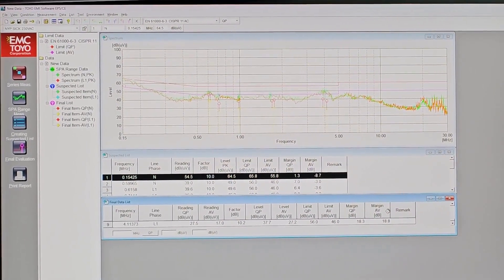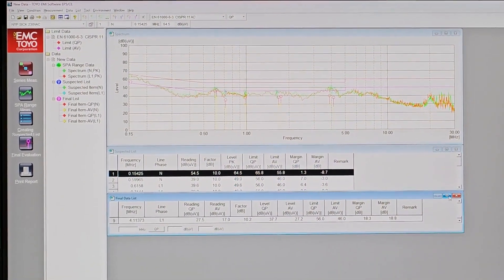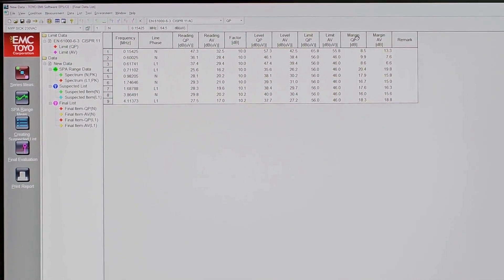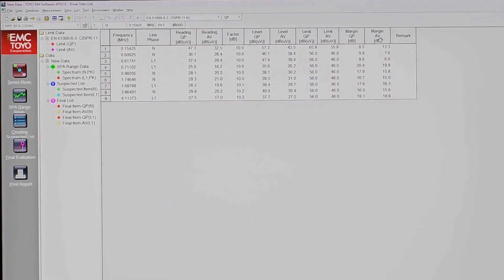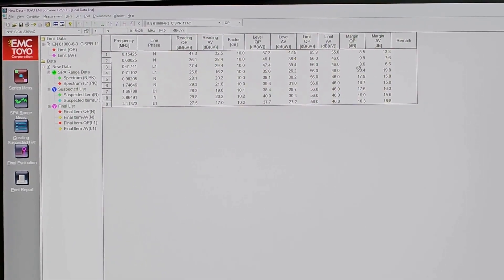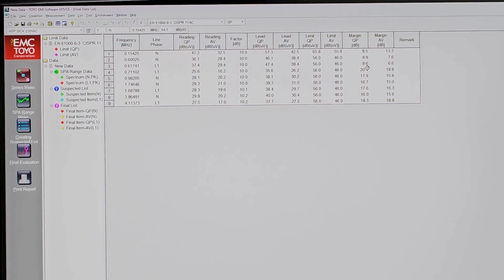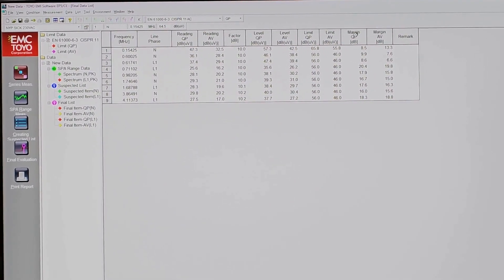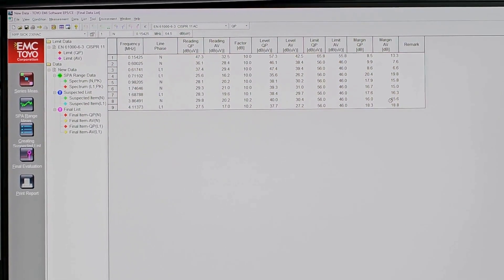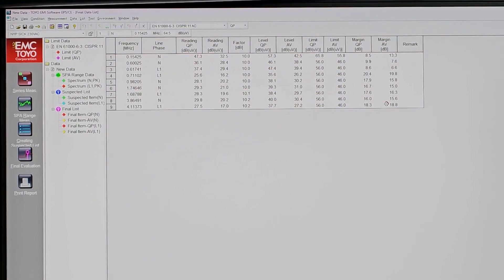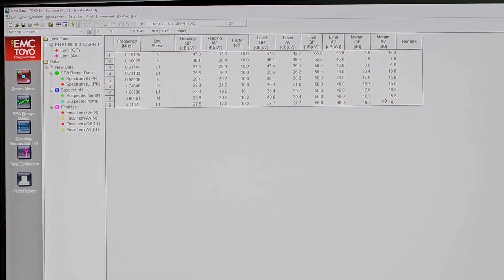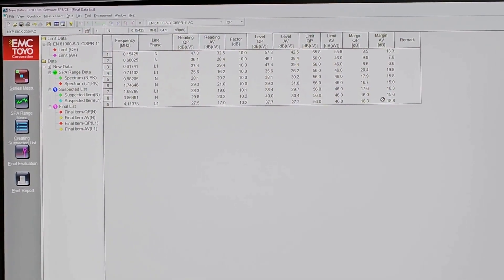We have now finished all the final evaluation. The key results to examine are the two margin values — quasi-peak and average. If the margin is a positive number, the DUT passed; the bigger the number, the more confident the pass. You can see that the DUT passed all the different frequencies — both quasi-peak and average passed all tests. I conclude that this DUT passed the CISPR 11 conducted emission test. Please help by liking and subscribing. Thank you.